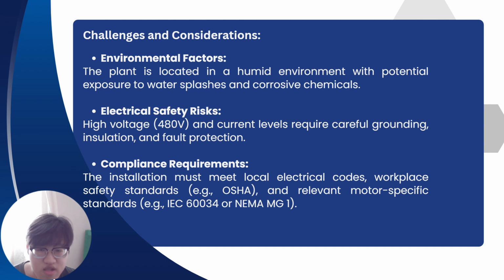Third, compliance requirements. The installation must meet local electrical code, workplace safety standards, for example OSHA, and relevant motor-specific standards, for example IEC 60034 or NEMA MG1. This means that different places have different standards. If he wants to start his installation, he must follow the local electrical code or standard to prevent safety issues in the local construction.